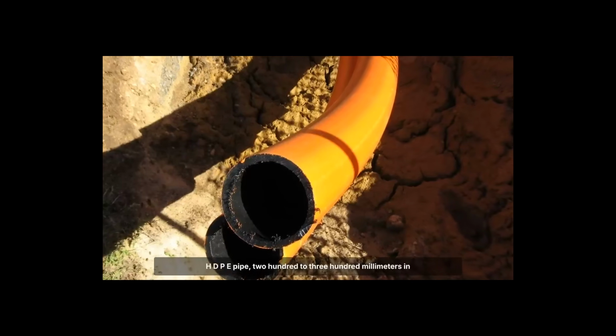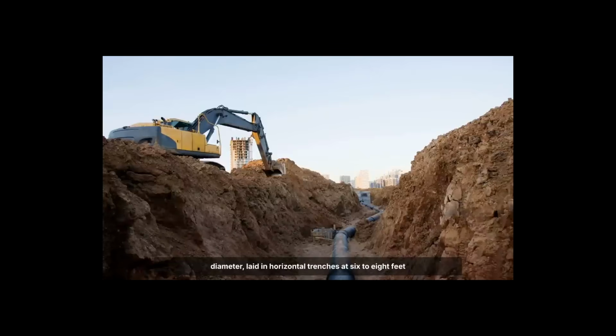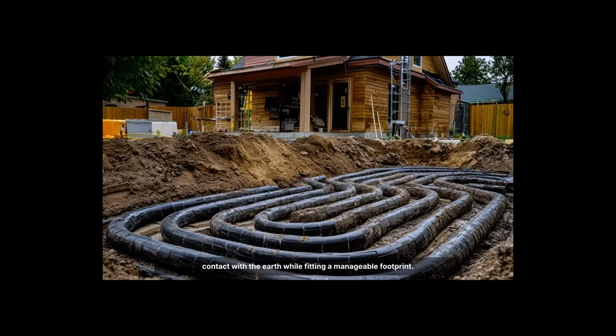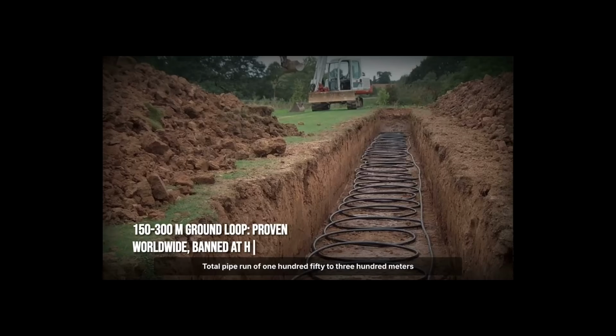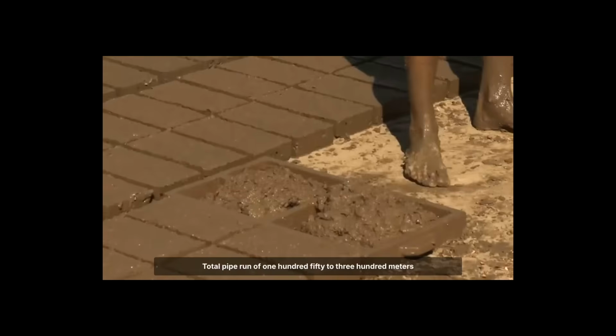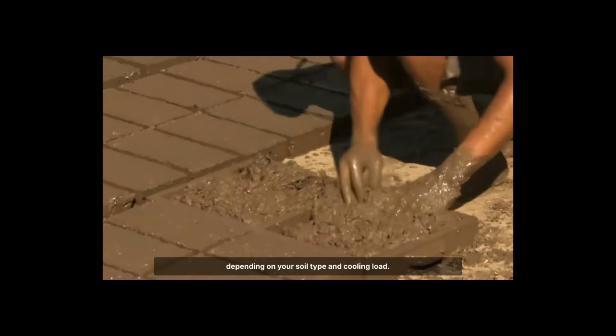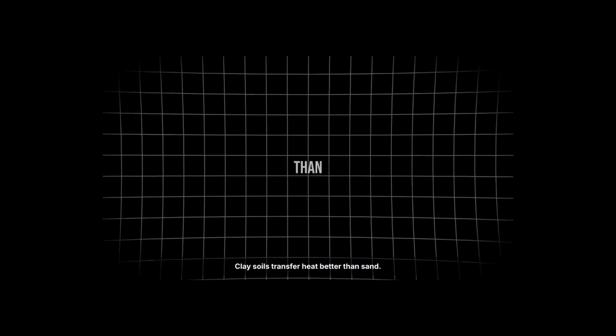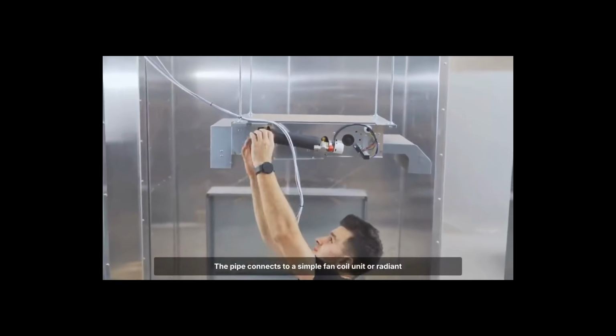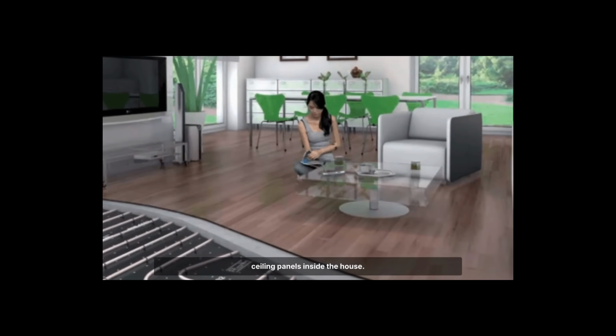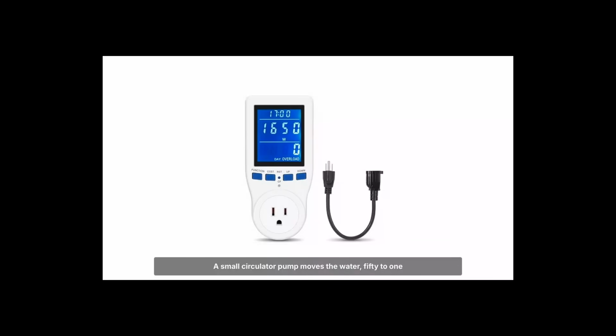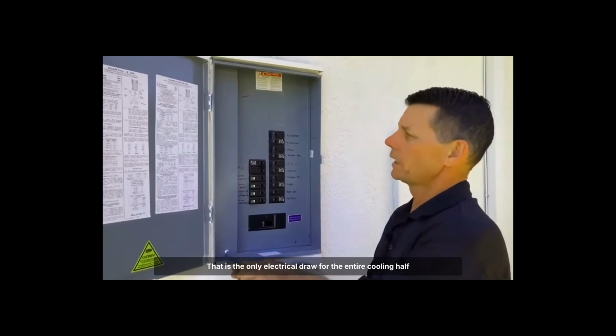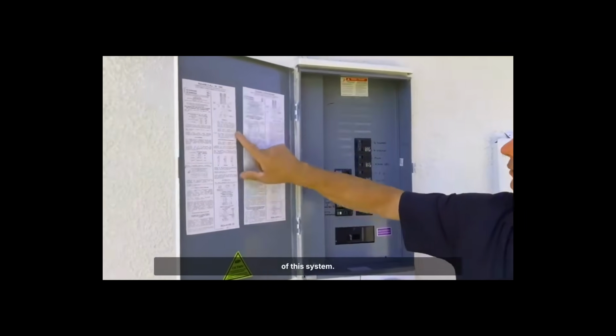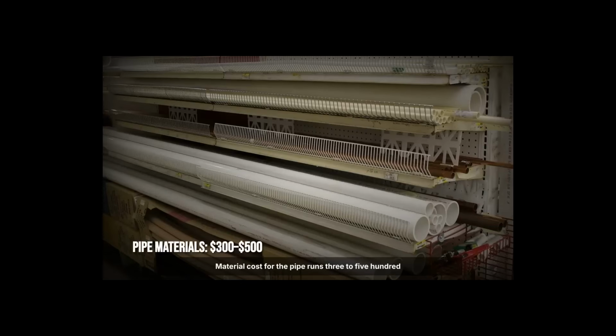HDPE pipe, 200 to 300 millimeters in diameter, laid in horizontal trenches at 6 to 8 feet deep. A serpentine or slinky configuration maximizes surface contact with the earth while fitting a manageable footprint. Total pipe run of 150 to 300 meters depending on your soil type and cooling load. Clay soils transfer heat better than sand. The pipe connects to a simple fan coil unit or radiant ceiling panels inside the house. A small circulator pump moves the water, 50 to 150 watts. That is the only electrical draw for the entire cooling half of this system. Material cost for the pipe runs $300 to $500.